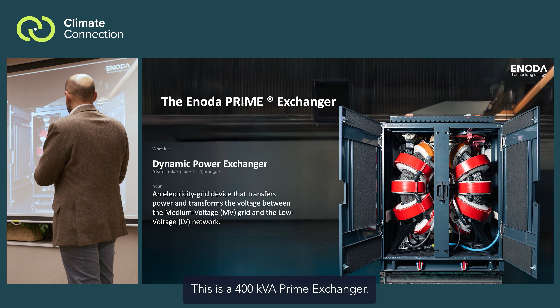So we need a new source of system stability, which is what we're delivering at Enoda. This is a 400 kVA prime exchanger. It replaces the distribution substation, the secondary substation at the end of your road. So it supports, say, 120 homes with single-phase power, or a building the size of this one, maybe this block, this building isn't that big, but a building that's roughly the size of this block with single-phase power, and it transforms voltage like a transformer does, but it also dynamically manages the electricity signal.